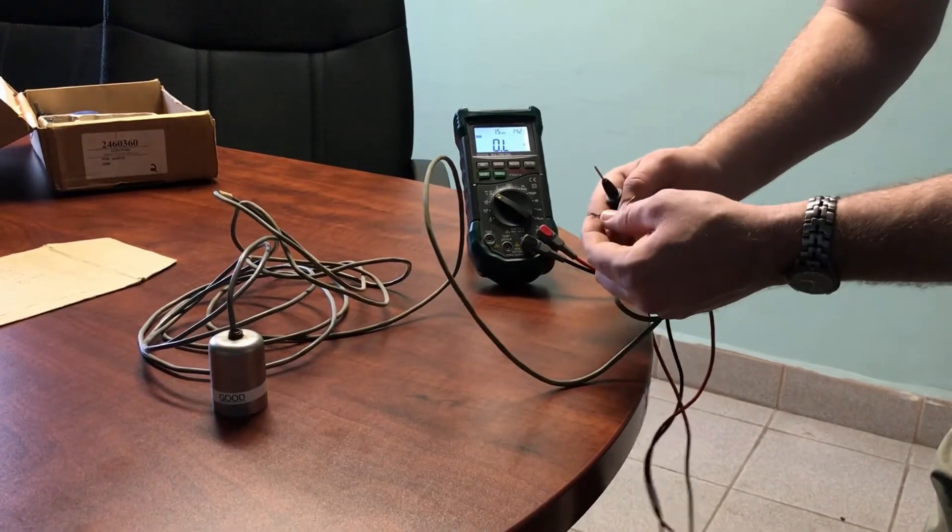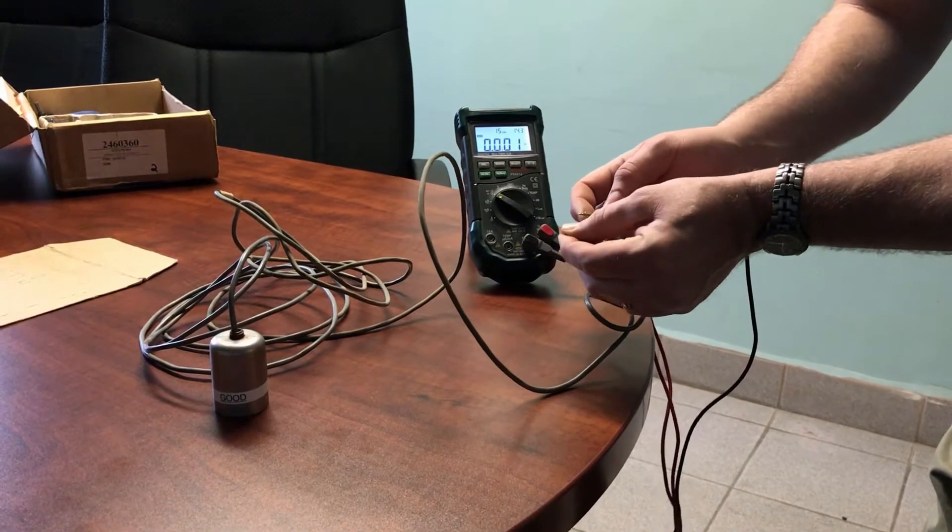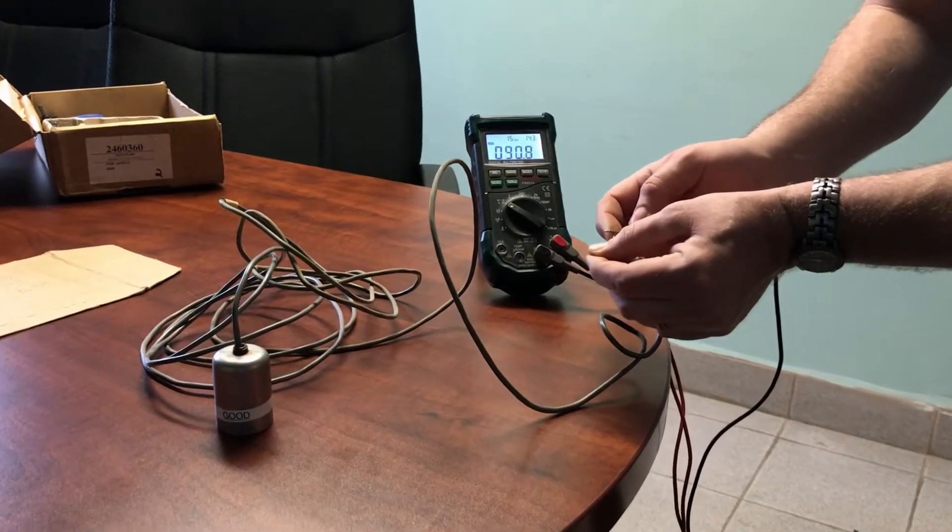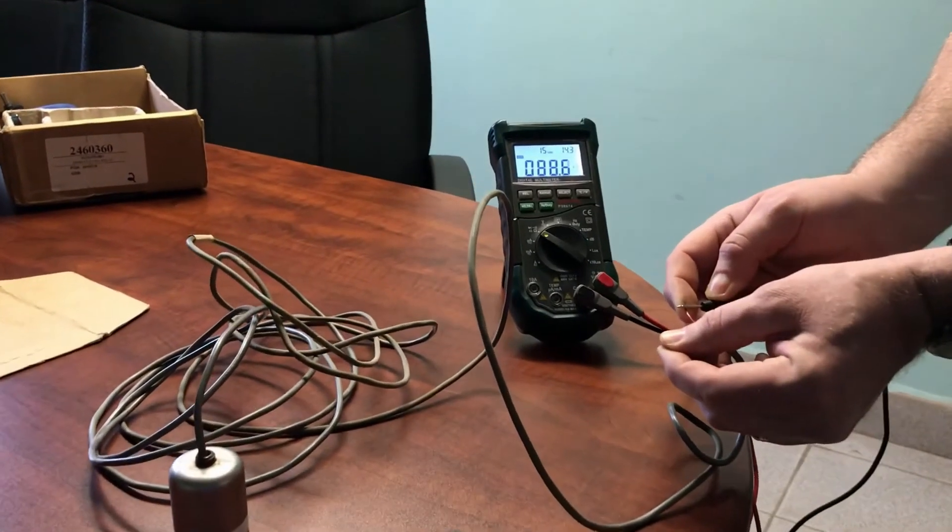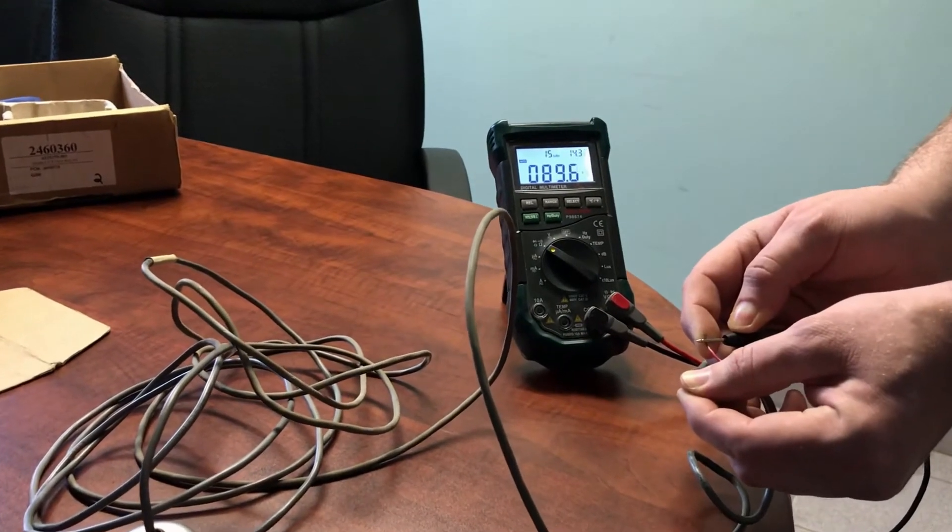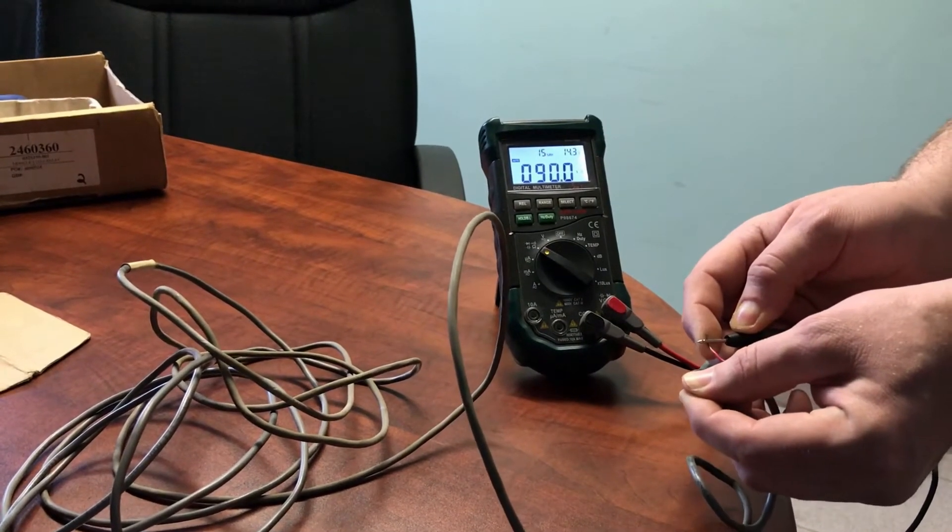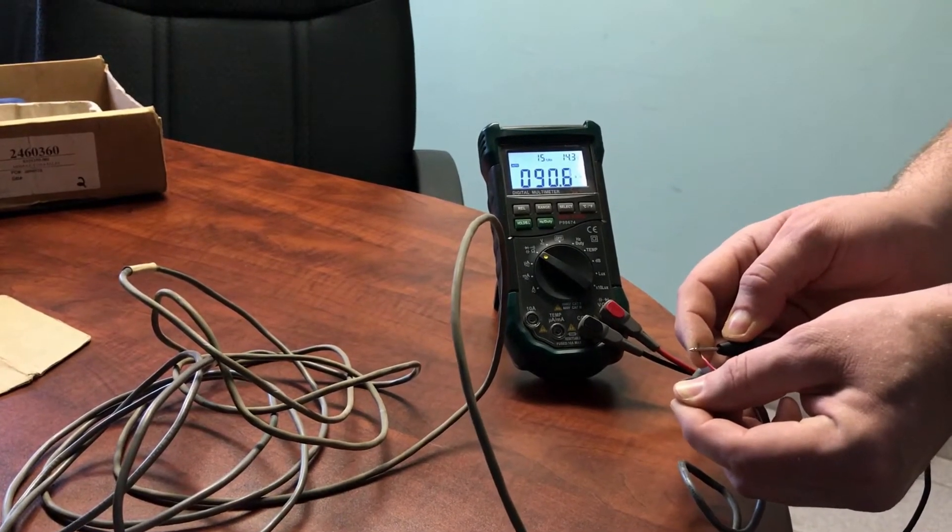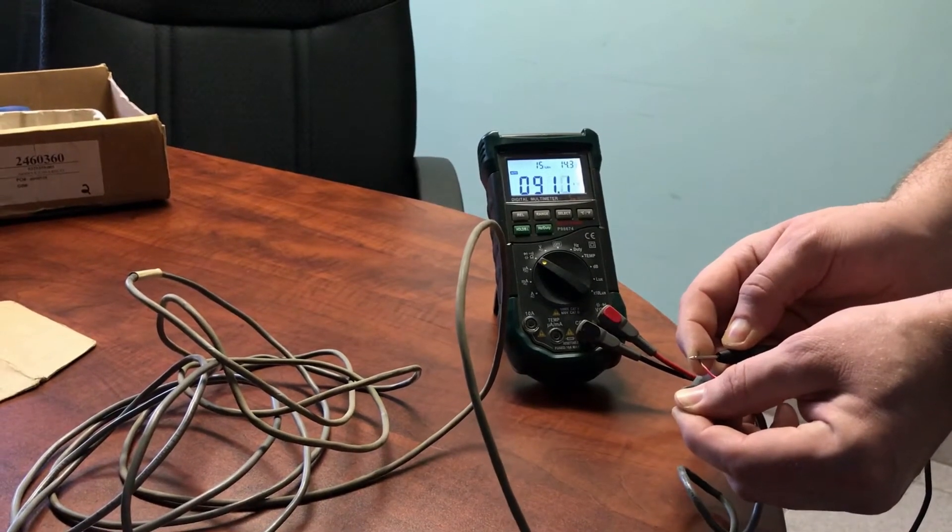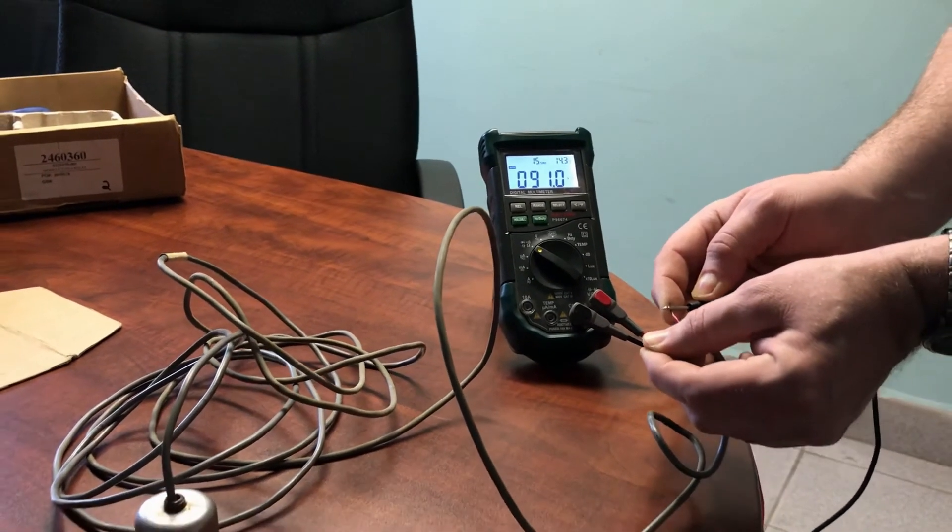At rest, the float is at rest and you'll see that this meter is now reading about 89 kilo-ohms. That's almost 100 kilo-ohms, somewhere between 55 and 135 kilo-ohms. That's at rest or not an alarm.